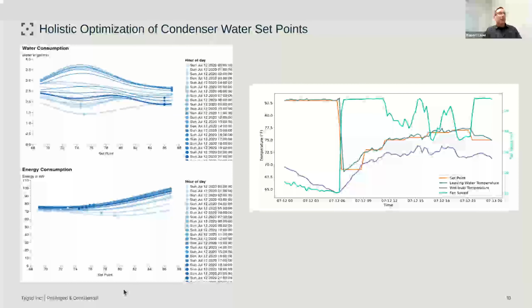If you were just looking at the lower picture and wanted to optimize electricity, you'd just find, for each of these hours, the minimum setting - the set point where you use the least electricity for all the equipment together. But if you also want to factor in water consumption, you have to consider both pictures at the same time and optimize that way.